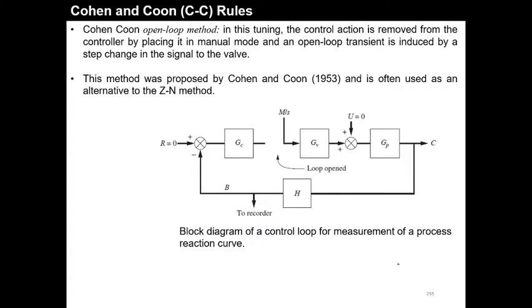We are going to discuss the Cohen-Coon open loop method first. In this tuning, the control action is removed — this is the controller, this is the final control element, and this is the process. First, we have to remove the controller from the control loop, disconnecting it and placing it in manual mode.